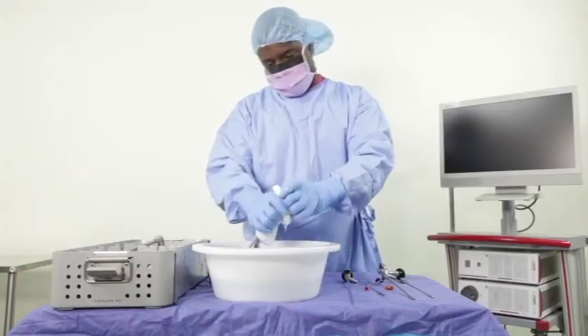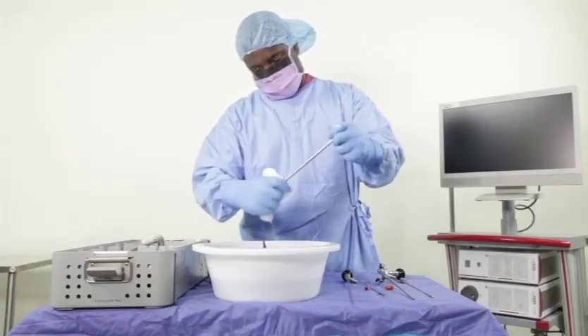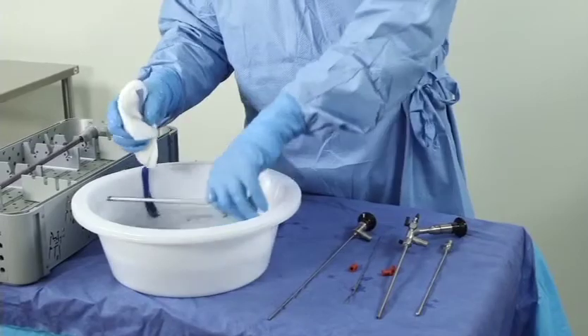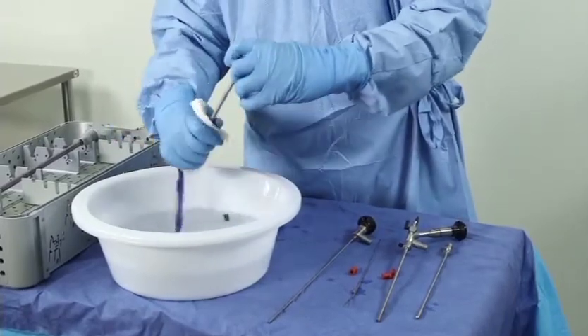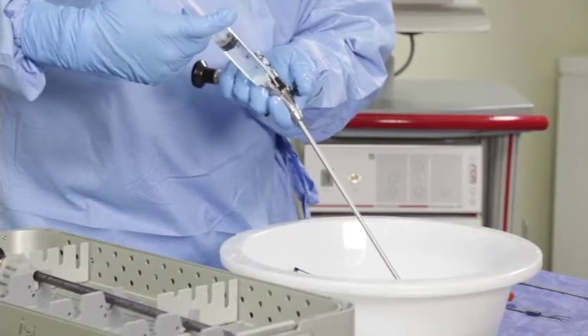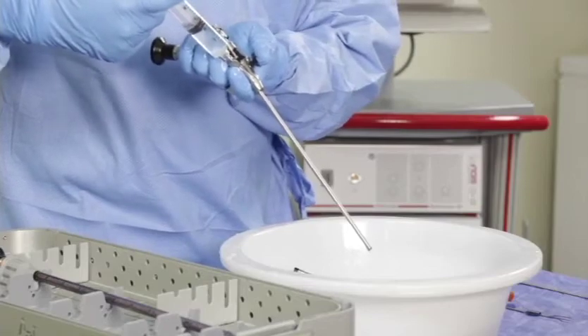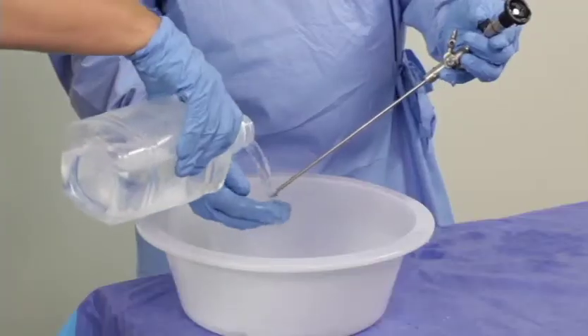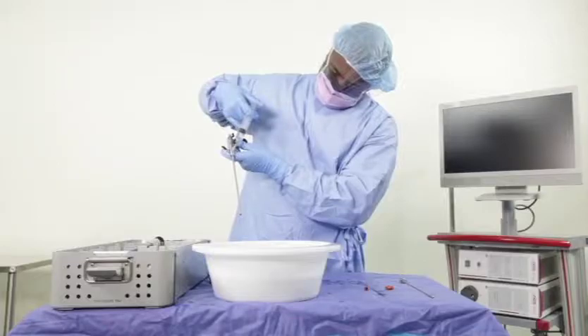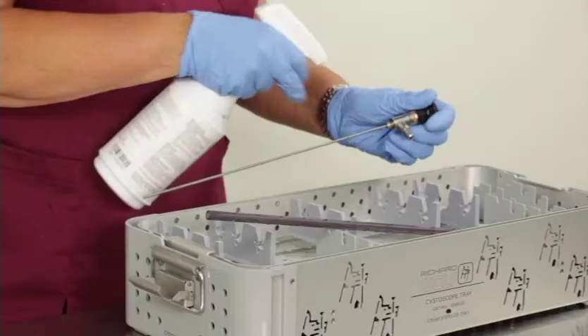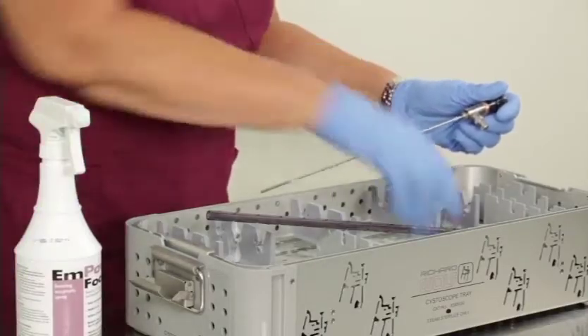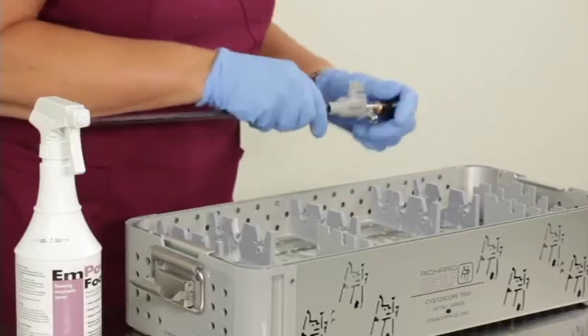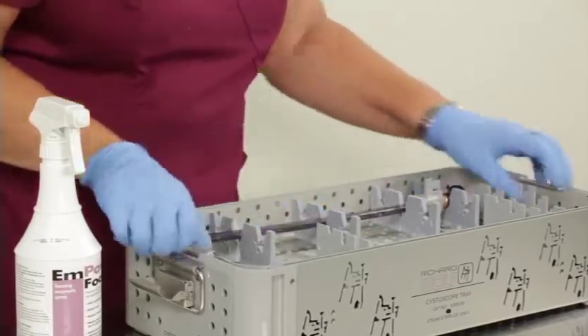Clean the endoscope surface with sterile water, tepid tap water, or enzymatic detergent, and a soft, lint-free cloth. Flush the channels with water or cleaning solution and a 20 cc syringe. Rinse the endoscope surface and channels with water to remove any residual debris and detergent. You may use a pre-treat spray that has been validated by Richard Wolf instead of this manual pre-clean process.